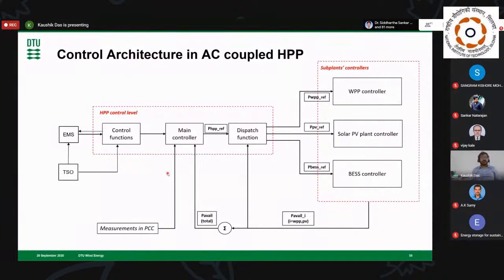But now, with EMS coming in, we are not operating at the maximum power point like we saw before with the battery. Rather, EMS gives signals every 15 minutes or every hour on how much the wind hybrid power plant should generate and how much energy it should store, and the TSO communicates any requirement for curtailment or additional grid services.